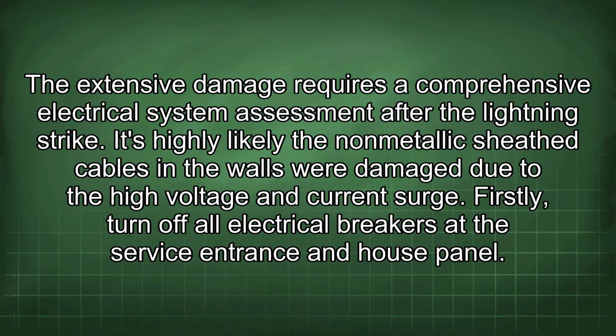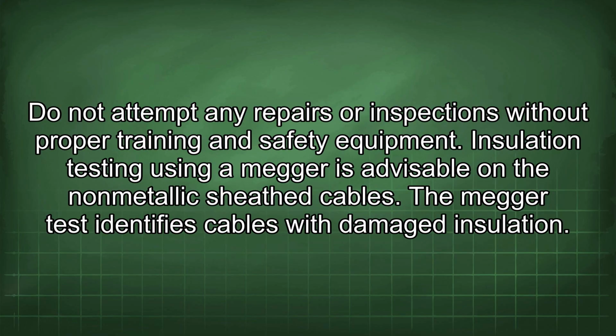The extensive damage requires a comprehensive electrical system assessment after the lightning strike. It's highly likely the non-metallic sheath cables in the walls were damaged due to the high voltage and current surge. Firstly, turn off all electrical breakers at the service entrance and house panel. Do not attempt any repairs or inspections without proper training and safety equipment.